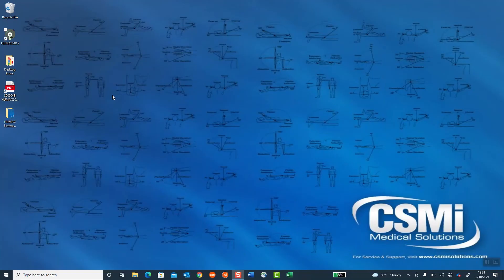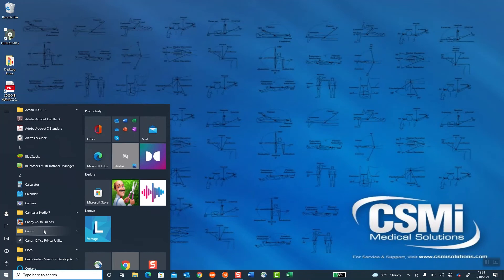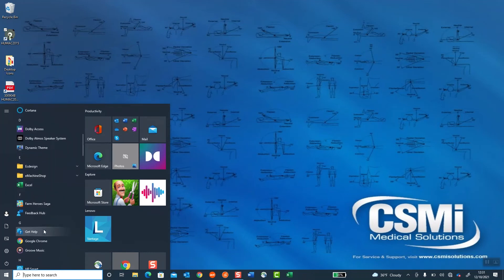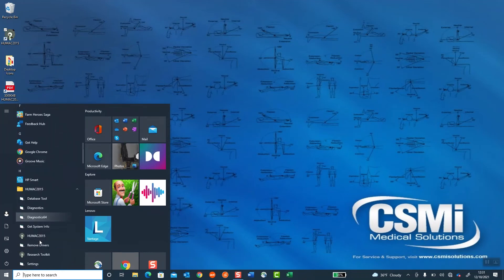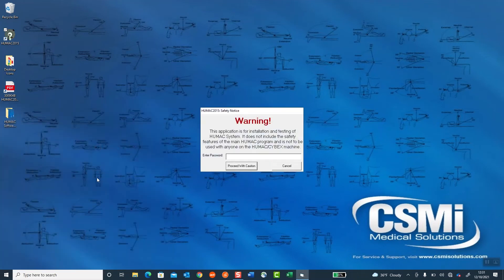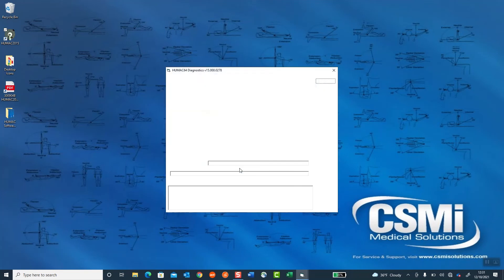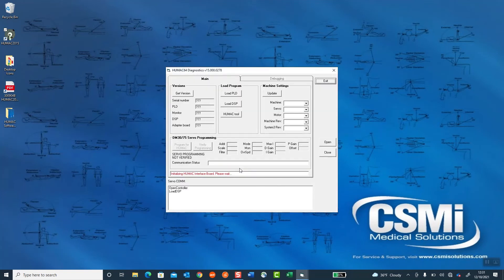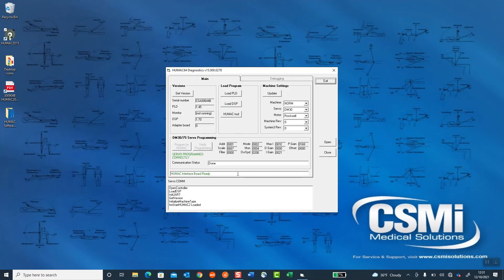File Exit. We're going to start the CSMI Diagnostics 64 by selecting Start, HUMAC, Diagnostics 64. We're going to enter the password, which is CSMIDIAG, CSMIDIAG. Select Proceed with Caution. The HUMAC is going to read the interface and read the servo amplifier. And once it's confirmed, this red line, which says Initializing HUMAC Interface Board, will turn green. HUMAC Interface Board ready. Select Exit.